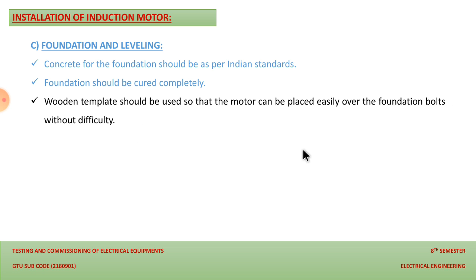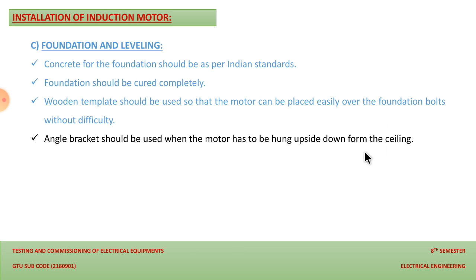Then an angle bracket should be used when the motor has to be hung upside down from the ceiling. This is an important point according to the requirement of the installation, to keep in mind when we need to install our motor differently. Then the next point that we should keep in mind is insulation resistance and drying out.